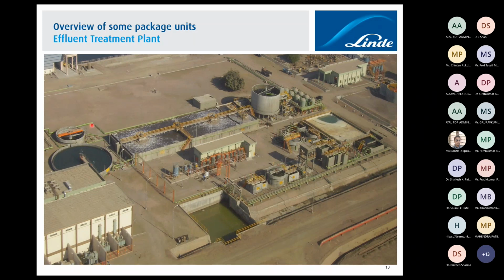And then this water is pumped back to the filters. So here you can see dual media filters and activated carbon, a pair of filters. And once filtration is done, you have some small storage, then you can pump it elsewhere, wherever you need to take this clean water. Typically this is by nature a package unit, but this is a miniature plant, or a plant within the plant. And this typical dimension is 50 meters long and some 28 meters wide. So it's a large package unit, I would say.